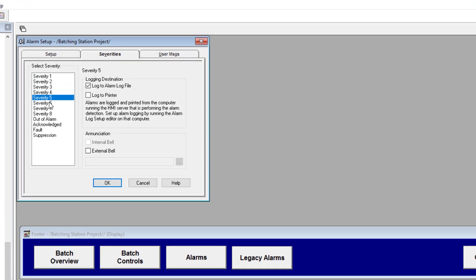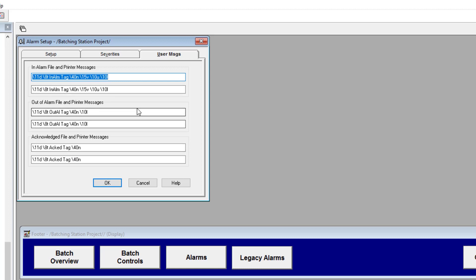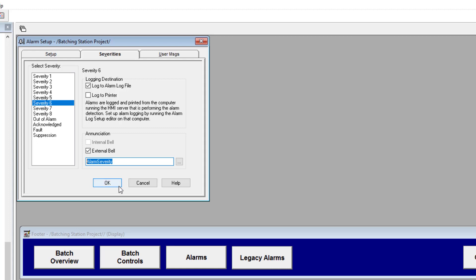That's how the two systems are working. Also, there's another listing for the legacy tag under HMI Tag Alarms. Another key note — on the severities, you can set them here. For instance, I'm using severity 6. You can also use an external bell: if you want to trigger an external horn or siren, that's where you tie in the tag you want to trigger. The message or user message I usually keep at default, but that's up to user preference and how your system is set up.